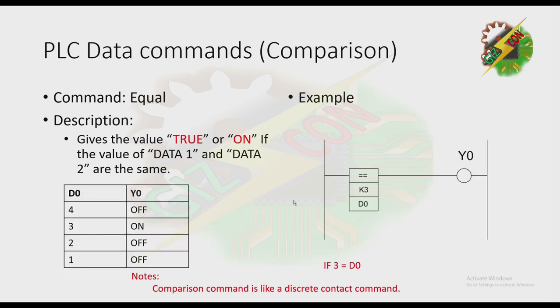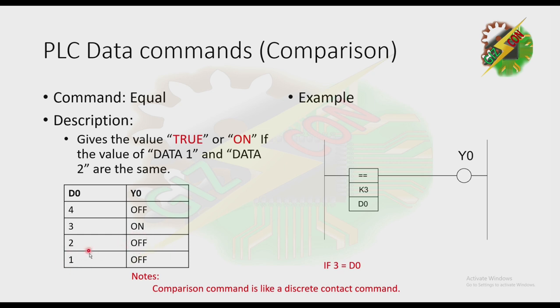In the example, the command '== K3 D0' means: if 3 is equal to D0, the value is true and Y0 will turn on. From the table: if D0 is 4, it is not equal to 3 so Y0 is off; if D0 is 3, they match so Y0 is on; if D0 is 2, Y0 is off; and if D0 is 1, Y0 is off.